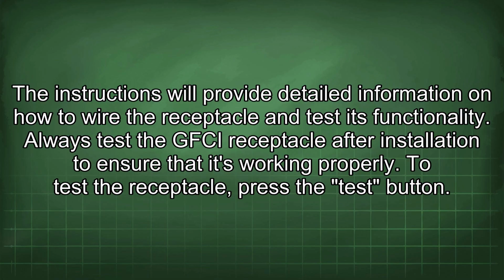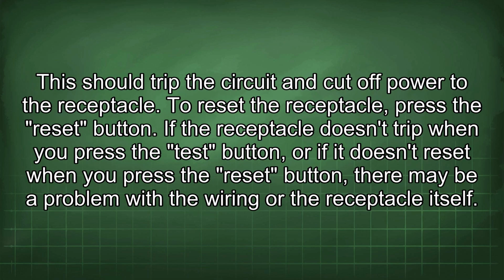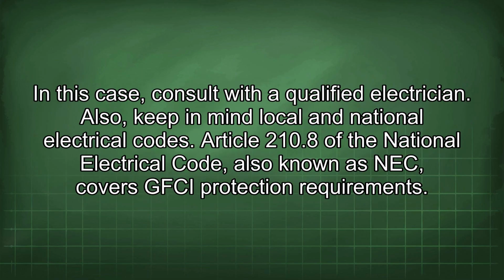To test the receptacle, press the test button. This should trip the circuit and cut off power to the receptacle. To reset the receptacle, press the reset button. If the receptacle doesn't trip when you press the test button, or if it doesn't reset when you press the reset button, there may be a problem with the wiring or the receptacle itself. In this case, consult with a qualified electrician.